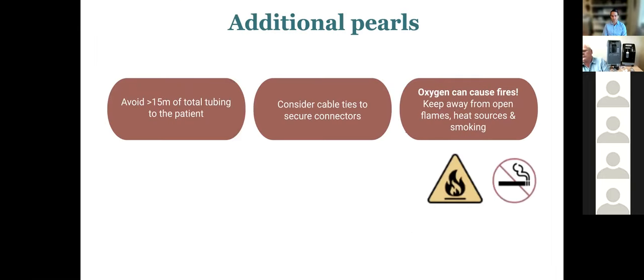A couple of additional things just to highlight. Check the manufacturer's specs, but try to avoid using more than about 15 meters of total tubing length to the patient. Consider using something to secure the connections to prevent your oxygen tubing from blowing off or disconnecting from the flow meters. You could think about using cable ties. And just to reiterate, oxygen can cause fires if it's around an ignition source, so please make sure to position these in a safe place.